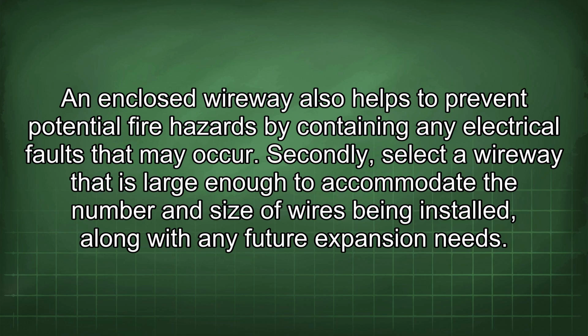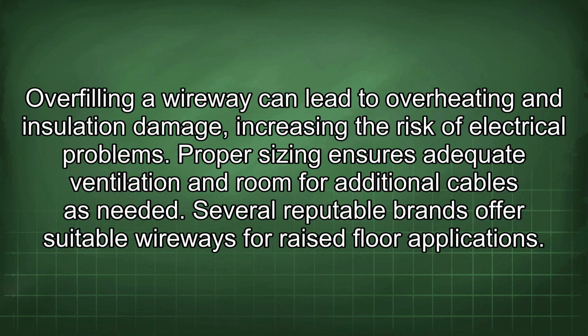Secondly, select a wireway that is large enough to accommodate the number and size of wires being installed, along with any future expansion needs. Overfilling a wireway can lead to overheating and insulation damage, increasing the risk of electrical problems. Proper sizing ensures adequate ventilation and room for additional cables as needed.